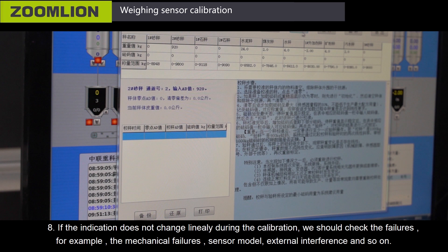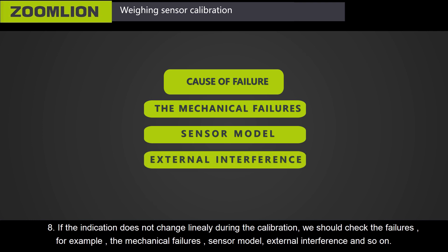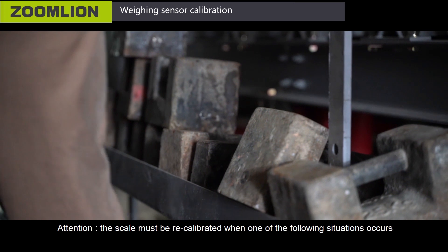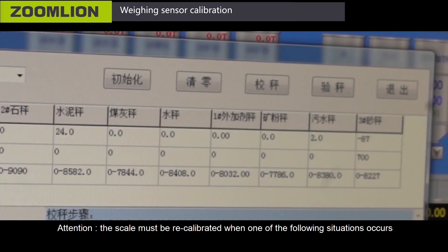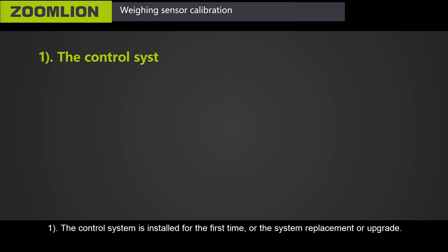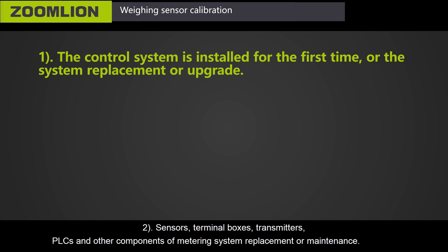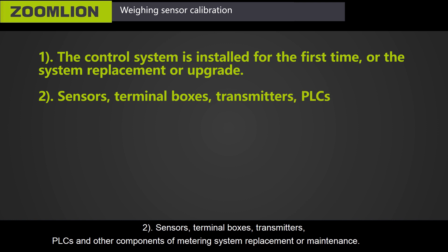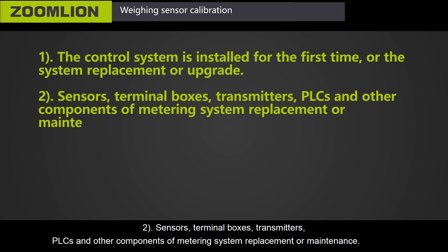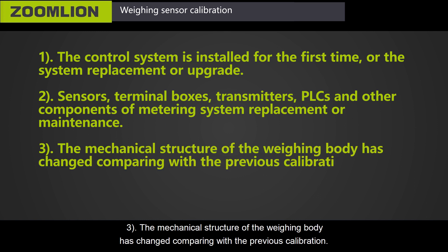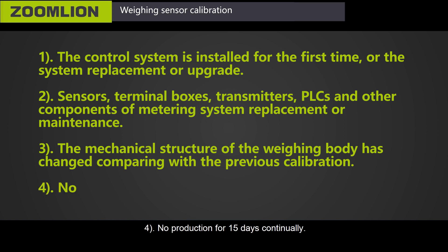Eighth, if the indication does not change linearly during calibration, check for failures such as mechanical failures, sensor model issues, or external interference. After resolving failures, recalibrate. Note: the scale must be recalibrated when any of the following occurs — the control system is installed for the first time, or the system is replaced or upgraded; sensors, terminal boxes, transmitters, PLCs, or other metering system components are replaced or maintained; the mechanical structure of the weighing body has changed since the previous calibration; or there has been no production for 15 continuous days.